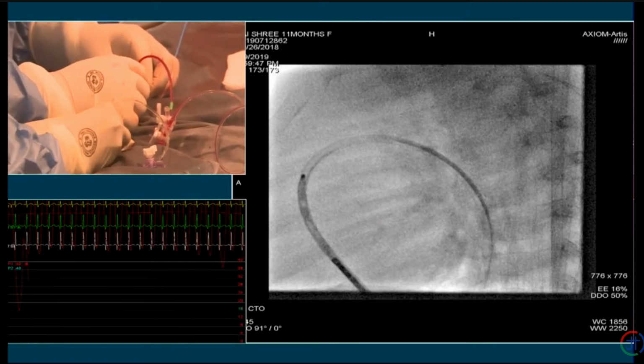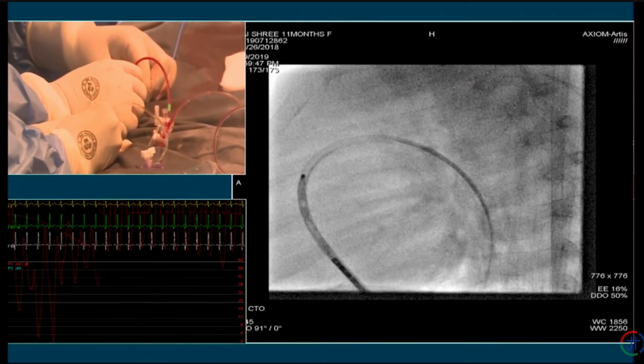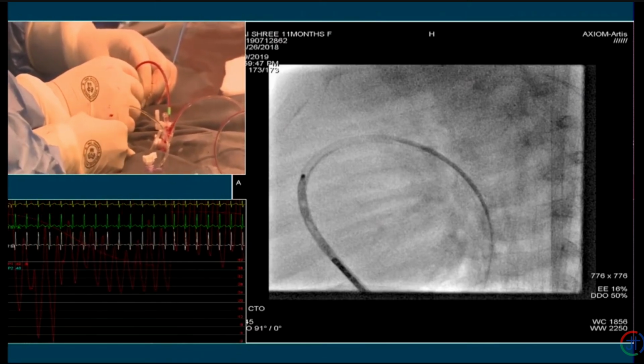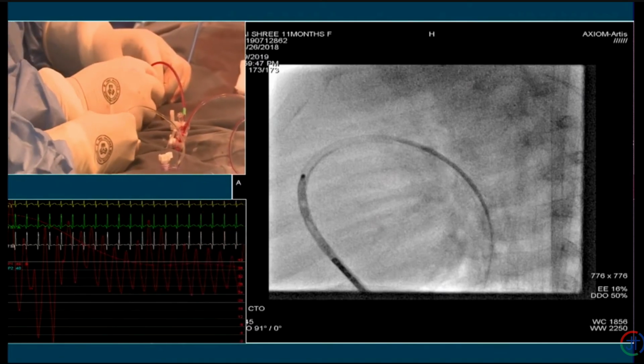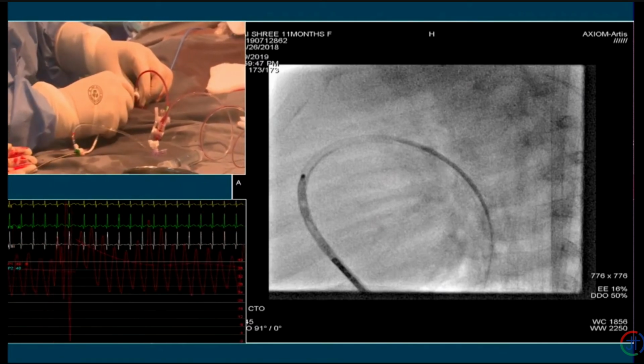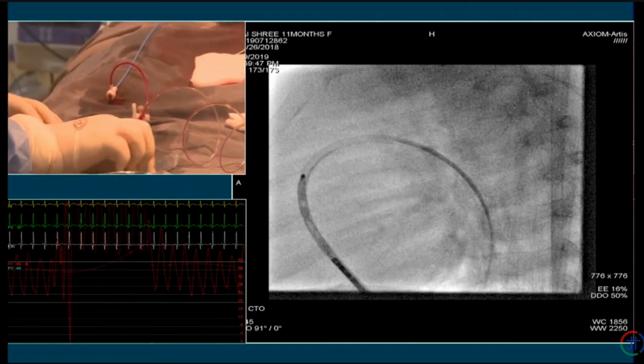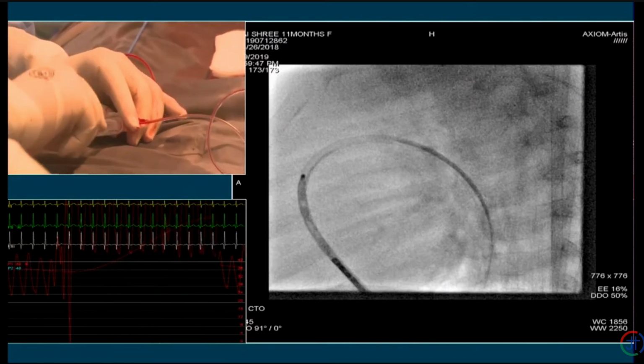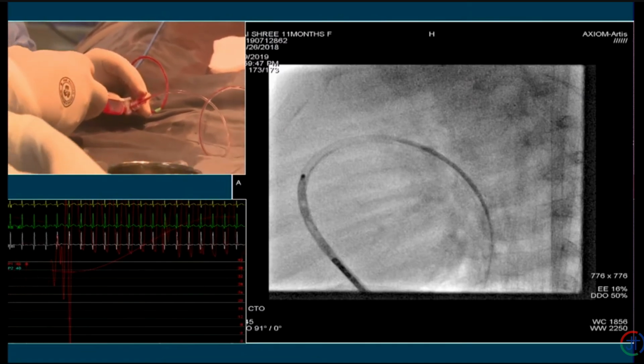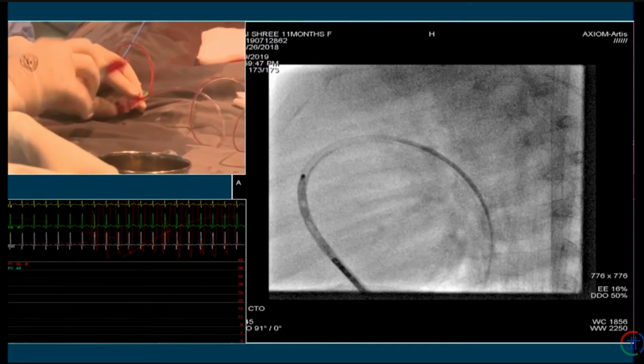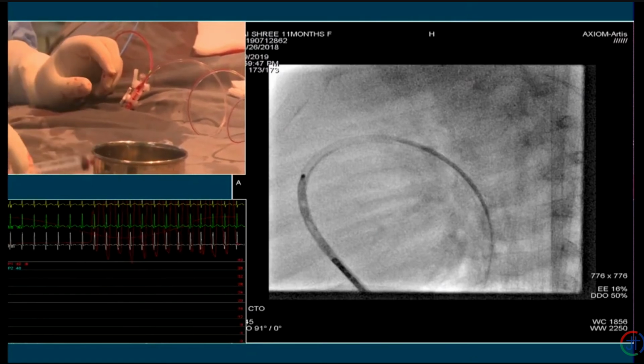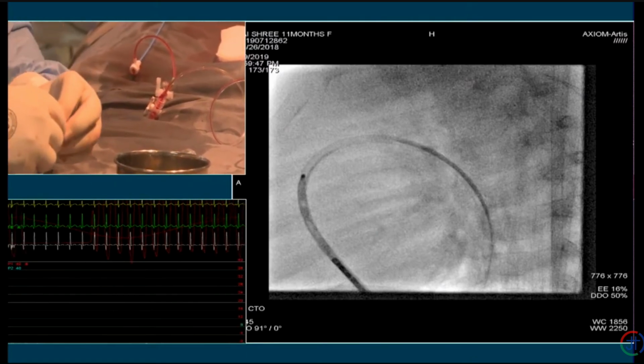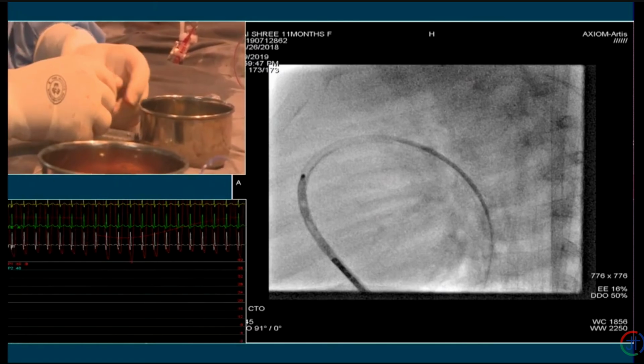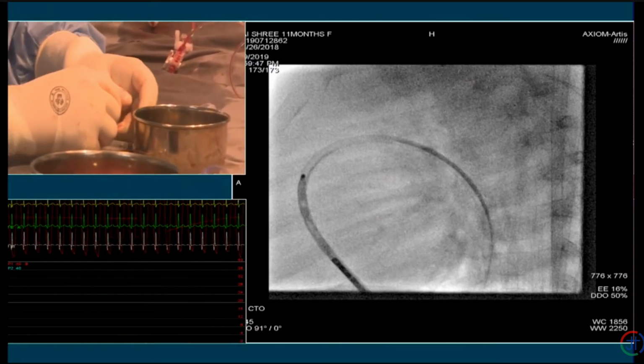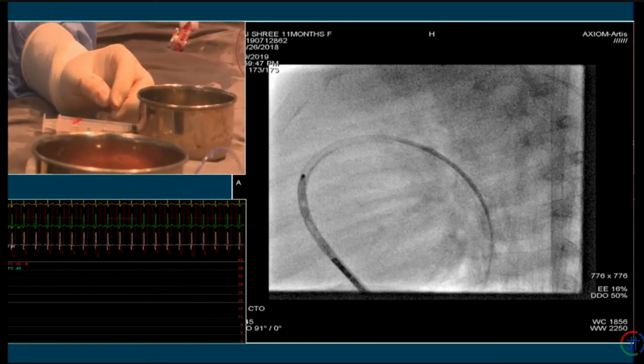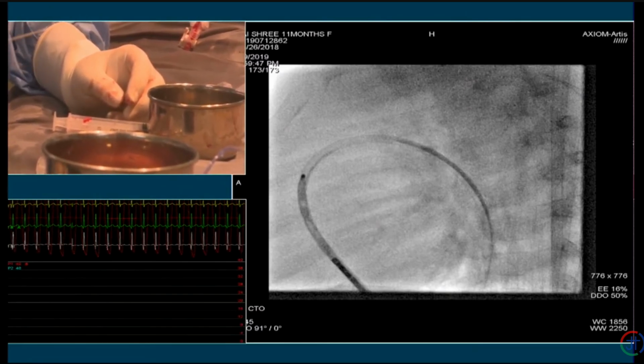Point taken. Let's see. There was some problem when they were loading the device. As you can notice on the screen, there was air in the system, so they're pulling it back and reloading it. Most of the time, what we usually do is we measure the ampulla on the echo itself. We try to measure the ampulla from the arch view and make a guess of the maximum size, because most of the sizing when we are using venous access is done by echo.